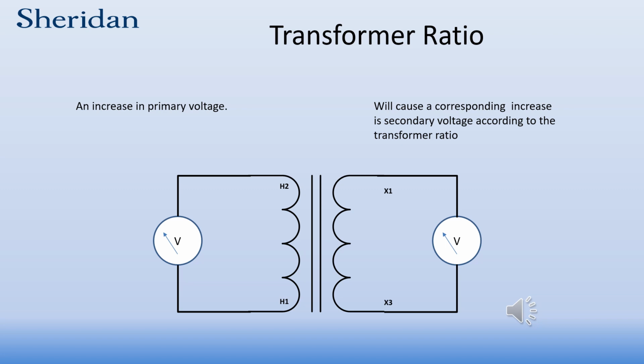Now, if you're going to test for transformer ratio to see if it's okay, what is required is a variable voltage power supply. You seek out the high voltage connection. Well, how do you do that? That would be the winding with the highest ohmic value. And what you do is put the variable voltage supply across it and slowly increase the amount of voltage applied to the transformer and measure the voltage on the secondary.